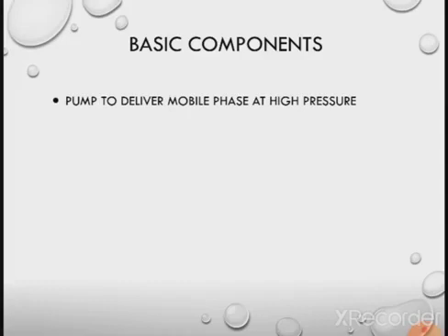Now the next part we want to learn is the injection system. The injection system is a very important part that is required to introduce the sample. As we know, the pump provides very high pressure, and at that high pressure we want to introduce the sample without disturbing or reducing the pressure. That's why we require a special injection system to introduce the sample, and this system is known as the Rheodyne system.